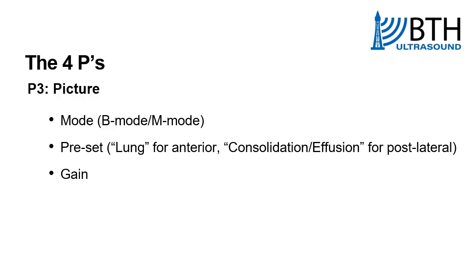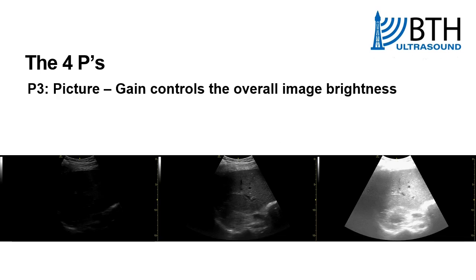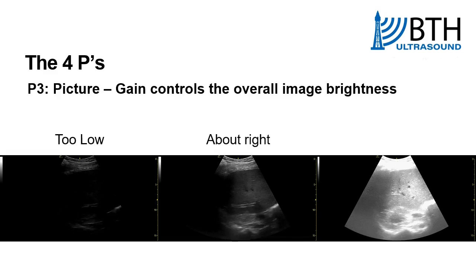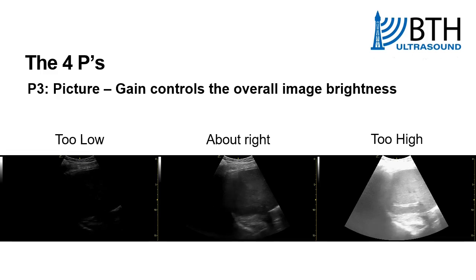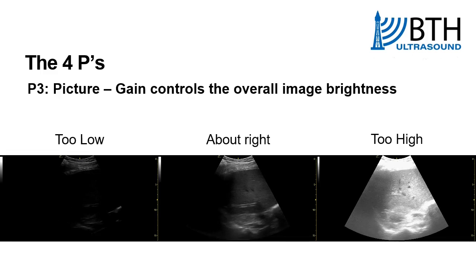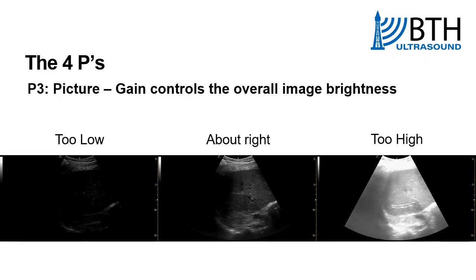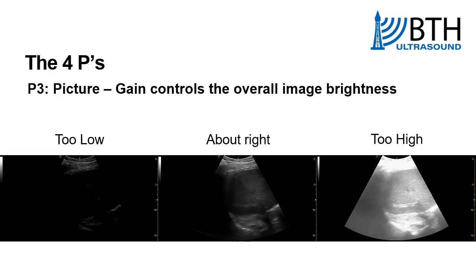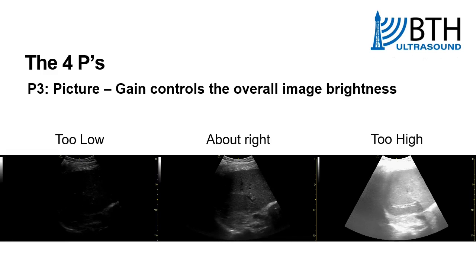We then go on to gain. This is in effect the strength of the signal coming back from the ultrasound machine and the machine's interpretation of that strength of signal. It dials up the strength, so it's almost like brightness to some extent. So you don't want the image too dark, where the gain is too low. You want to try and get it in a middle setting so that you can see all the structures that you want, and you want to avoid having the gain too high because the signal is too strong and you can't interpret the images quite as well. So here we have an image that's too dark, one that's about right, and one that is too high with the gain setting.